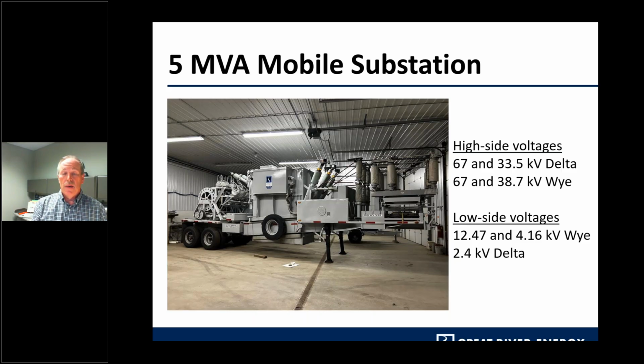This is an older mobile sub that was built in the 1950s, actually late 1959, and it has that 2.4 kV low side voltage to be used for melting ice on the transmission lines. What we do is calculate the line impedance and how much that 2.4 kV current could withstand to create enough heat and melt the snow and ice off our lines. We haven't used that too much now as technology has changed and there are new tools for getting rid of ice off our transmission lines. But back when we first purchased that mobile, that was one of the characteristics we wanted to implement, to free up the ice and snow from our transmission lines.